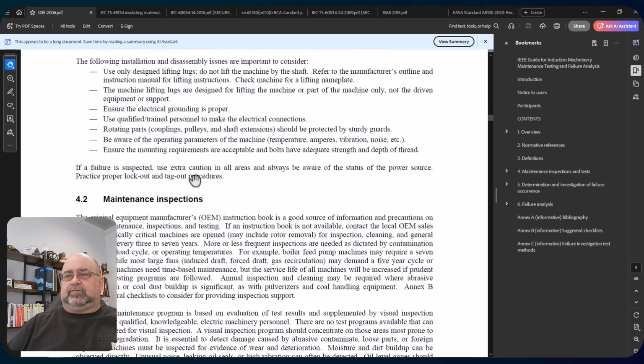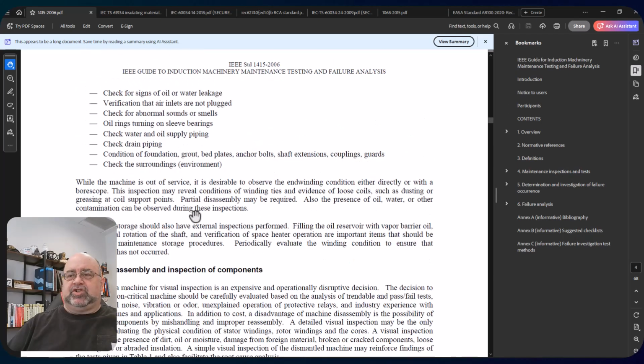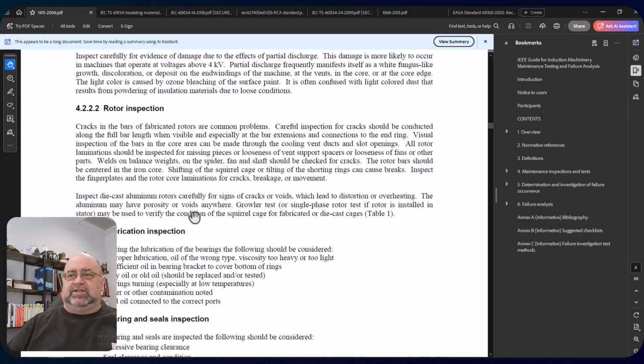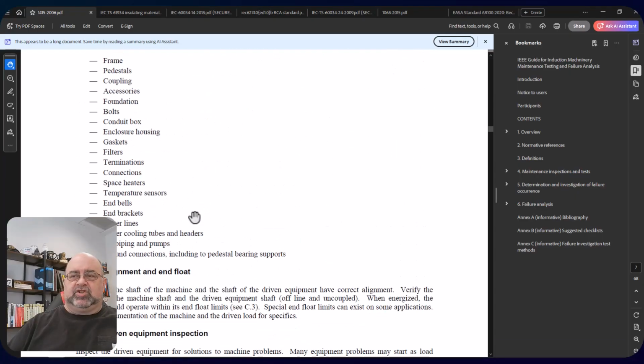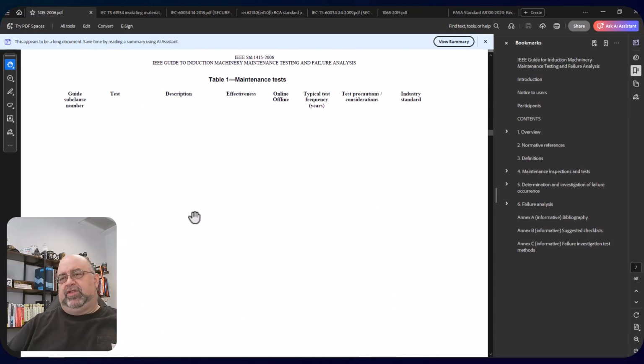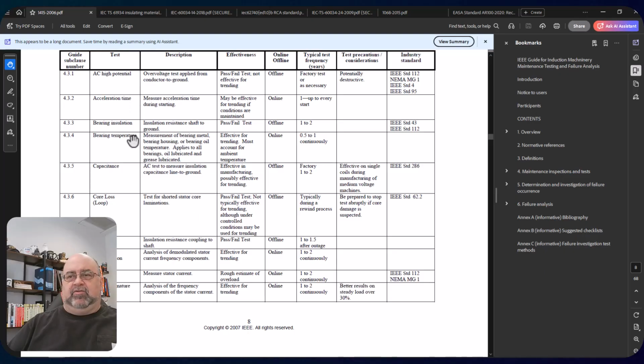So the maintenance inspections, that's where we got into the descriptions. One thing I had a problem with was it got broken down into individual components of a test. So AC high potential, that one would be separate. Potentially destructive means if it's not performed right, the amount of electrical pressure applied could damage the machine.